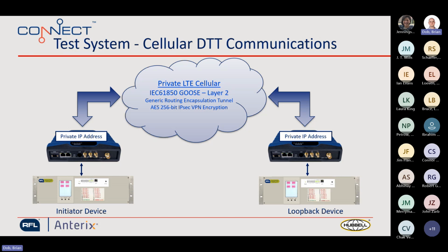Yeah. So this is a little bit more detail about the equipment used in this test setup. We're using the RFL GARD 8000 device to generate a 61850 GOOSE message. This is a layer 2 GOOSE message, and we utilized a device to relay this layer 2 GOOSE traffic and send it over the private LTE cellular network. In addition to that, we also utilized 256-bit IPsec encryption. So there's an encrypted VPN tunnel with generic routing encapsulation, and that is carrying the layer 2 GOOSE traffic end to end.